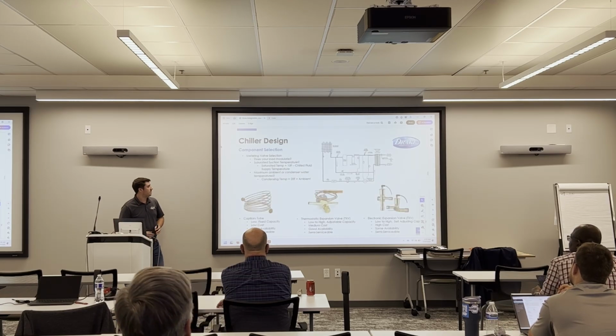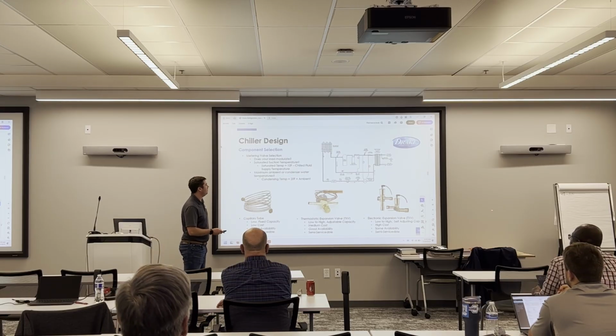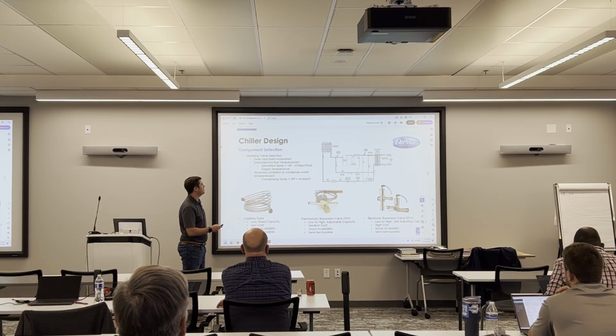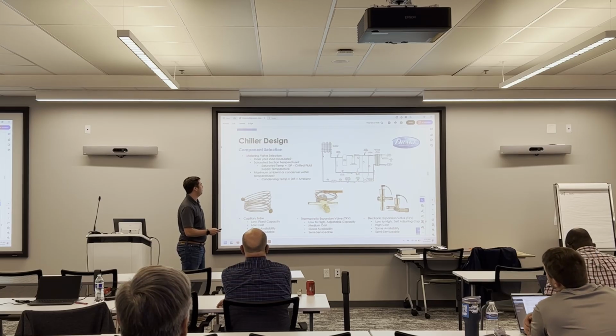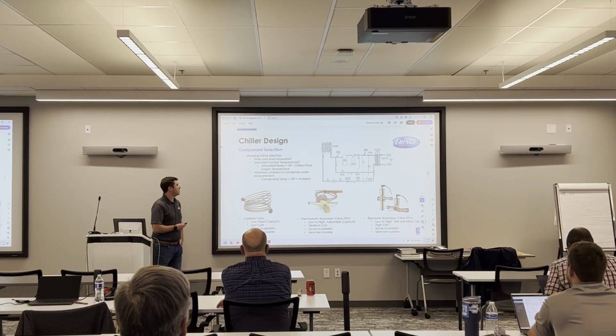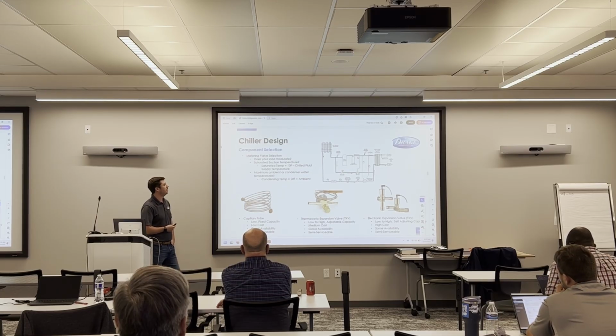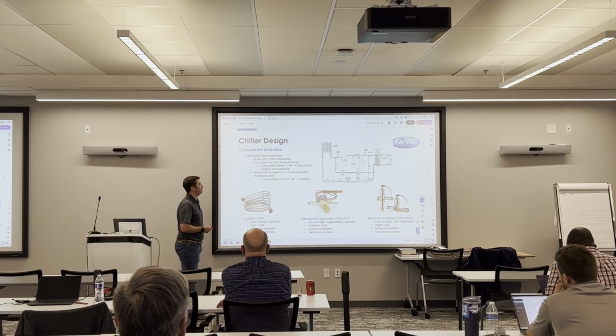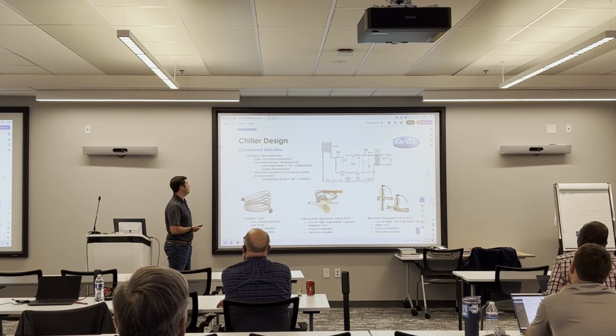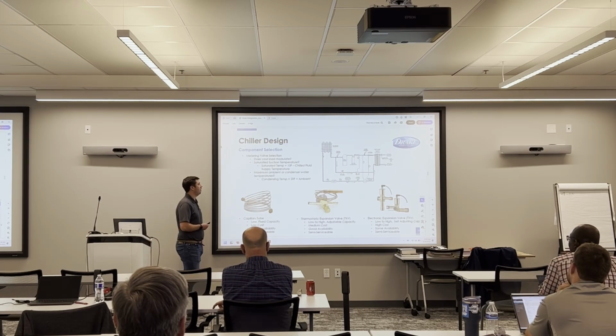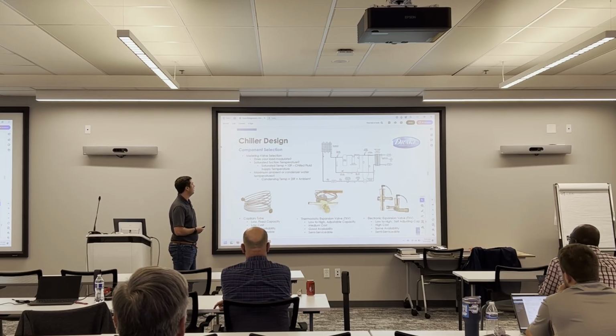All right. So now we'll get into the metering valve. So we're down here now. We just talked compressors, we talked condensers, now we're talking metering valves. Some questions we ask for the metering valves. Well, not really. These are mostly questions we ask ourselves. Drake generally handles the component selection for the expansion valve. So, is your load going to modulate? That's a good question to ask. What are your saturated suction temperatures that you're trying to get to? Well, we'll know that if we know the chilled fluid temperature. Maximum ambient or the condensing water temperatures, that's something we need to know as well. Again, that condensing temperature is just going to be 20 degrees plus your ambient temperature.